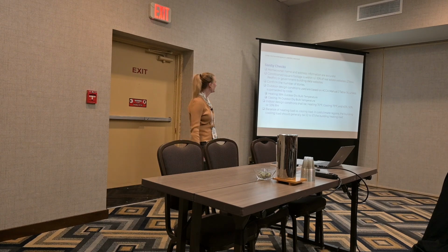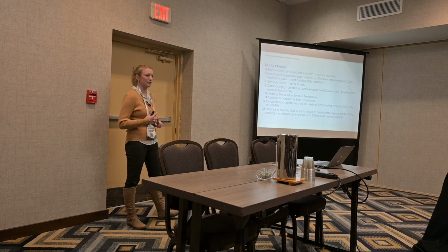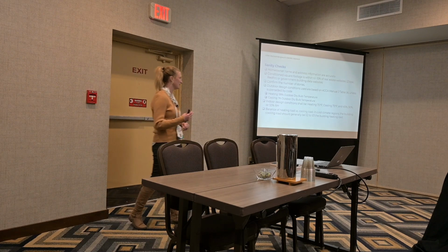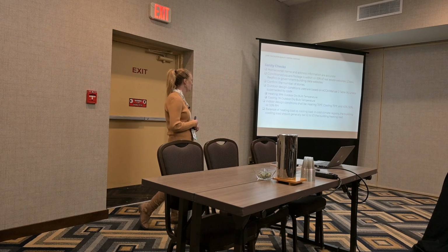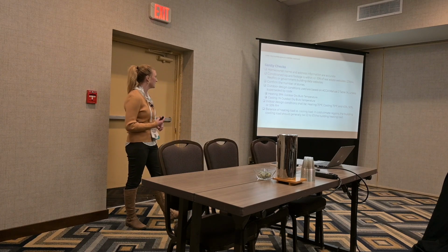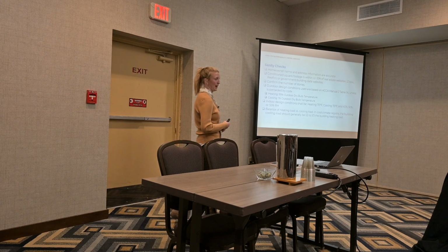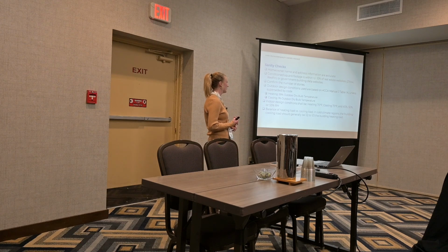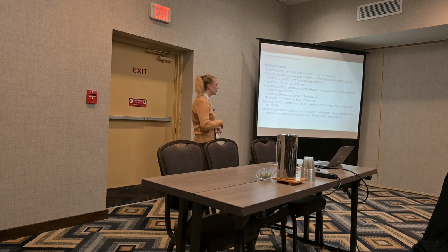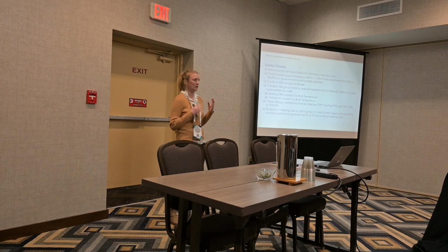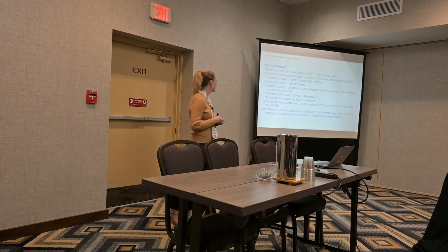What's the difference here? Confirm number of stories. Outdoor design conditions used are based on ACCA Manual J tables. Indoor design conditions used should be based on ACCA. So heating should be 70 degrees. Cooling should be 75 with a relative humidity of 45, 50, or 55. You shouldn't be putting in inputs based on that homeowner who wants their house at 85 degrees. You should be doing it based on what the standard requires.